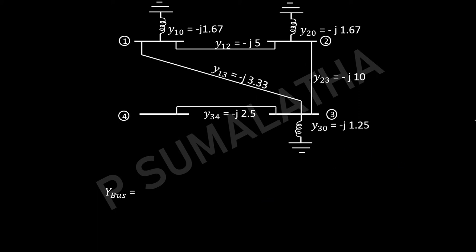So let us form the Y-bus. We have 4 buses, so the Y-bus matrix will be 4 by 4. Y11 is the sum of admittances connected to the first bus — three lines are connected — giving minus J1.67 plus minus J5 plus minus J3.33, which totals minus J10. For Y12, we take the negative of the admittance between buses 1 and 2: minus of minus J5 equals plus J5. If you have any confusion, mark the bus numbers on the matrix.